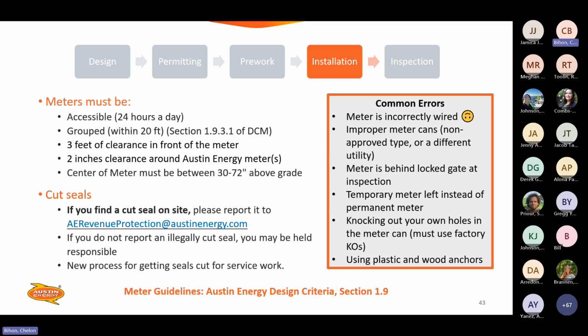Common errors: meter is incorrectly wired, improper meter cans, not an approved type or a different utility, meters behind a locked gate at inspection, temporary meter left instead of permanent meter, knocking out your own holes in the can (you must use factory KOs), using plastic and wood anchors. Please double check our approved list of meters, as there was a change in the past 3-4 months. We did quit permitting a specific type of meter can.